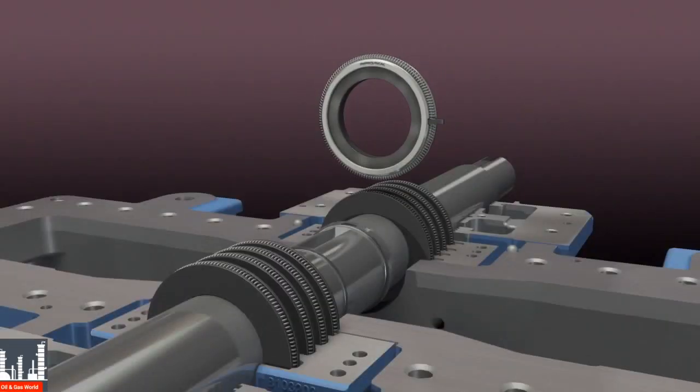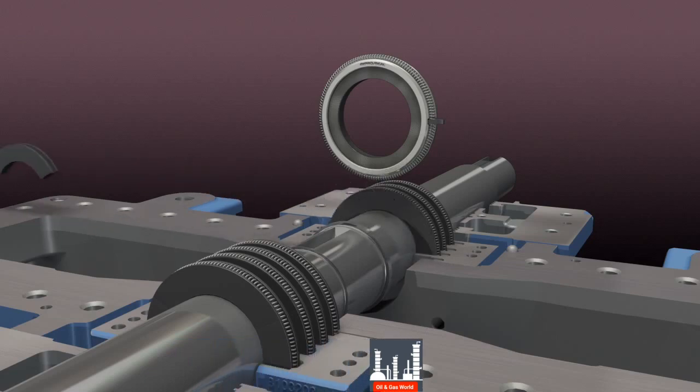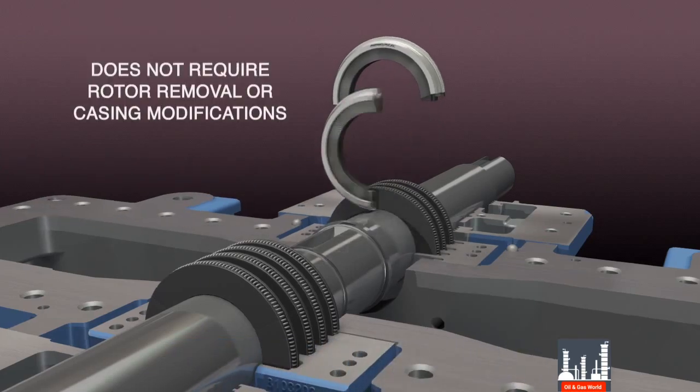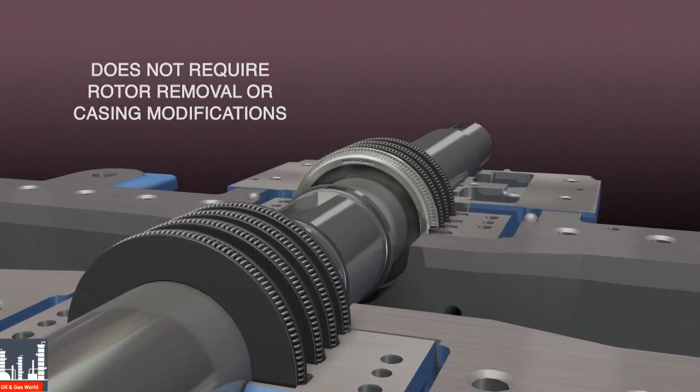Designed as a drop-in replacement for carbon rings, the Sentinel floating brush seal utilizes a split design that does not require rotor removal or costly casing modifications.